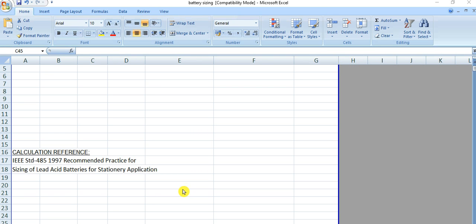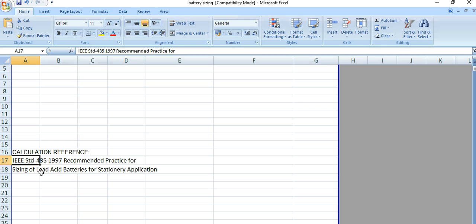Today I will discuss the battery sizing calculation for industrial applications, particularly lead acid batteries. This video covers the sizing calculation of lead acid batteries for stationary applications, following IEEE standard 485. IEEE 485 is for lead acid battery sizing calculation, while IEEE 1115 is for nickel cadmium batteries.